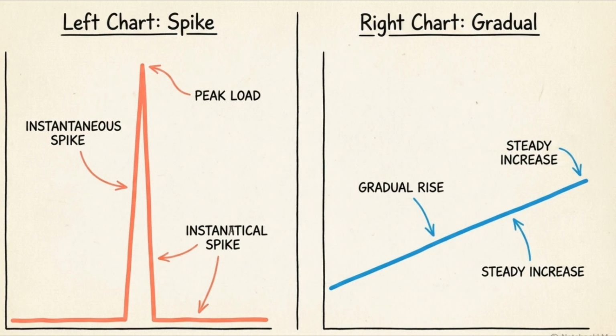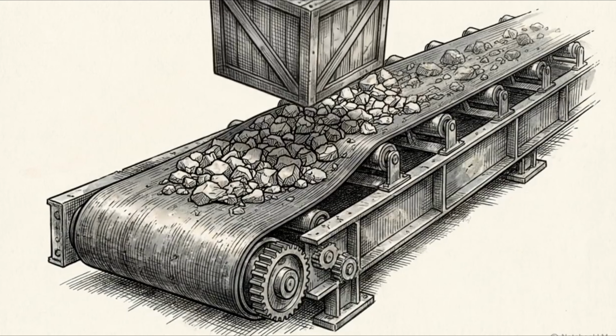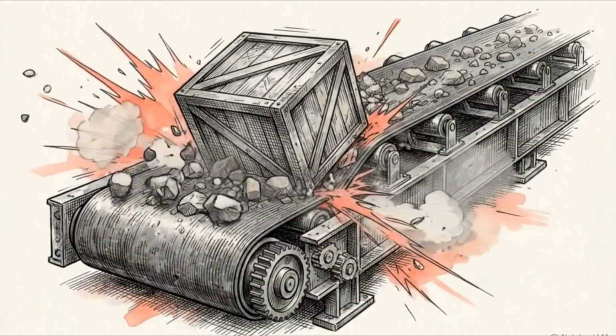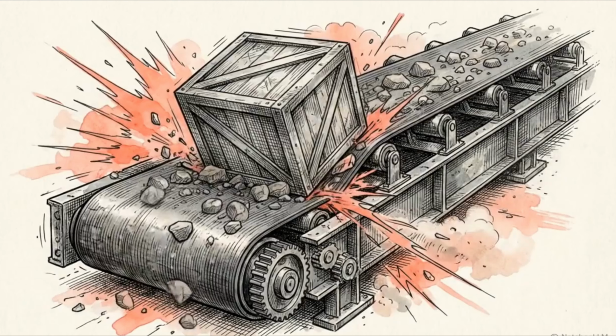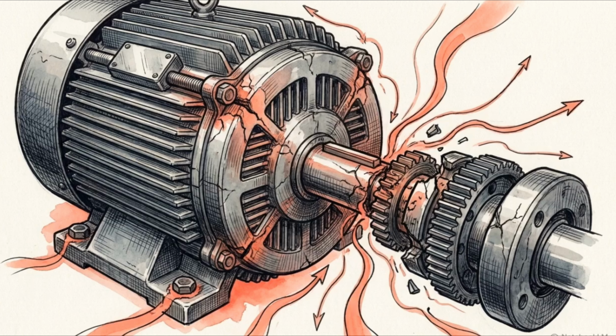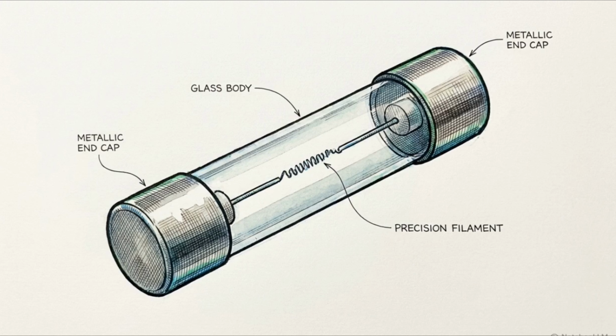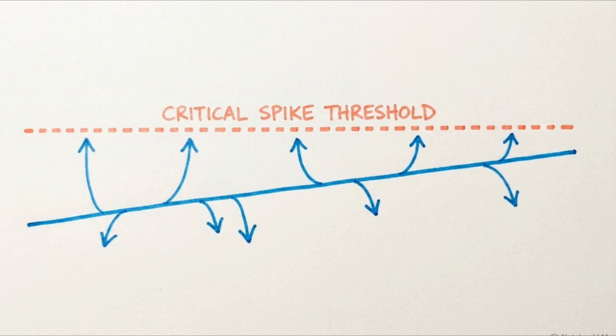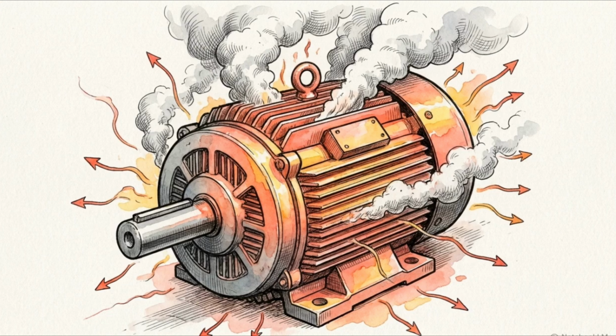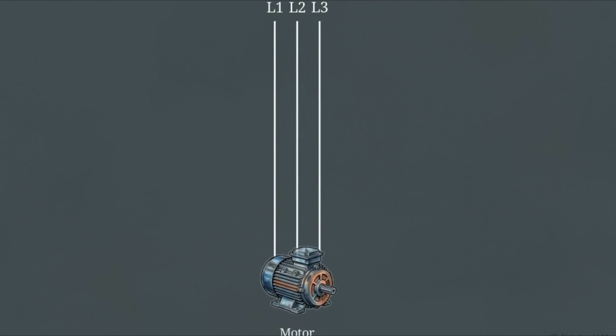While fuses handle sudden electrical spikes, they respond differently to a current increase that occurs as a slow, gradual crawl. Consider a heavy industrial conveyor belt powered by our three-phase motor. If a heavy object falls and jams the belt, the machinery stops moving. The motor continues trying to spin, drawing more and more electricity to force the unmoving load forward. Our high-speed fuses will not trigger here. The steady climb in current is too slow to snap the sacrificial wire, allowing the motor to eventually melt from the inside out. To solve this, we add our final component, the overload relay, placed right before the motor.